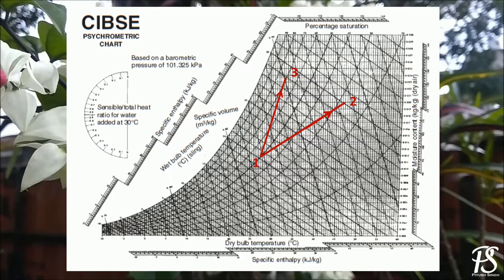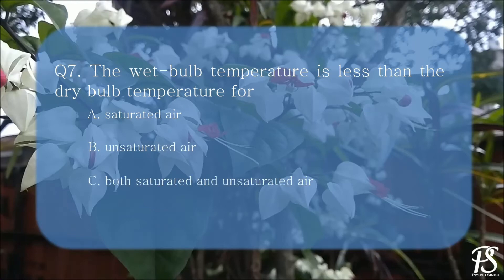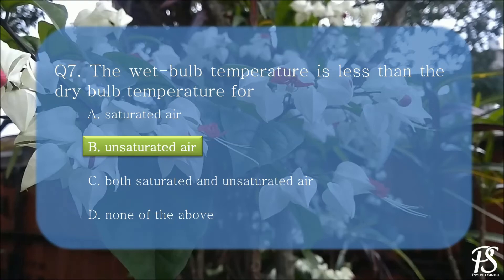Whether the relative humidity will increase or decrease depends on the sensible heat factor. For a process with a higher sensible heat factor, the relative humidity decreases. Whereas for a process with a low sensible heat factor, the relative humidity increases, because in that case the humidification process is more dominant. Regarding Question 7: the wet bulb temperature is less than the dry bulb temperature only for unsaturated air. As already discussed, at saturation, both dry bulb and wet bulb temperatures are equal.